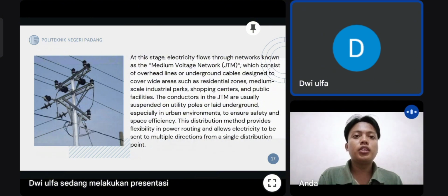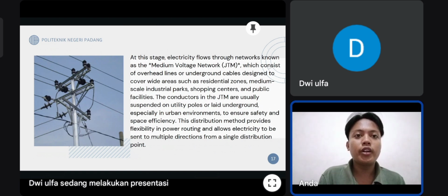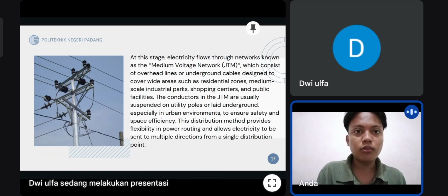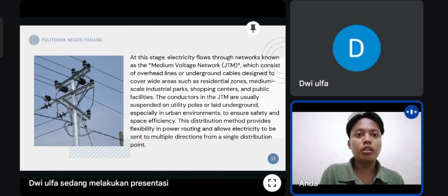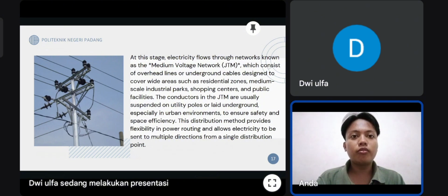This electricity flows through a network known as the medium voltage network, which consists of overhead lines or underground cables designed to cover wide areas such as residential zones, medium-scale industrial parks, shopping centers, and public facilities. The conductors in the medium voltage area are usually suspended on utility poles or laid underground, especially in urban environments, to ensure safety and space efficiency. This distribution method provides flexibility in power routing and allows electricity to be sent to multiple directions from a single distribution point.